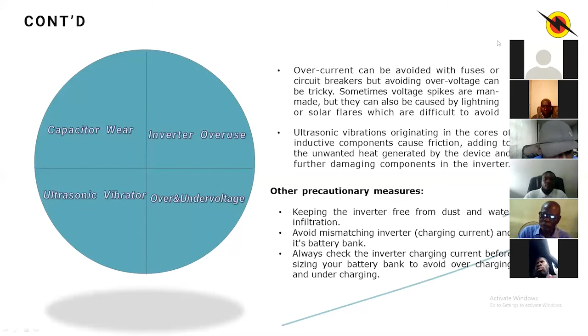Except if you have the central inverter, the type of inverter we have here in PSC Solar. The charging current is about 50 amps, and some of them can get up to about 70 amps. With this kind of inverters, you can use about 8 batteries at once and you're fine. 10 batteries, you're fine. So if you're stacking with a 24-volt system, you can stack up to about 800 amps battery bank and it will be fine. So you always need to check and compare, making sure the inverter is not mismatched against the battery bank. So the next one here is always check the inverter charging current before sizing the battery bank.